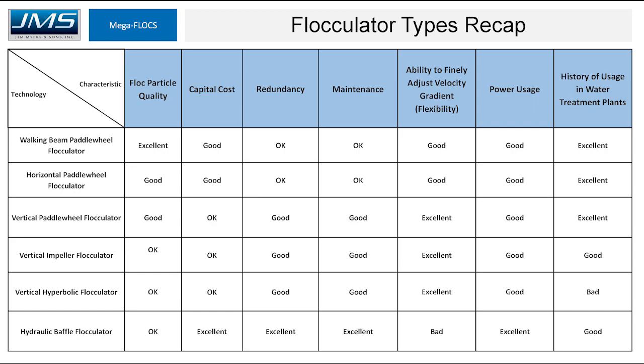To recap, each technology is listed by floc particle quality: walking beam flocculators are at the top, followed by horizontal and vertical paddle wheels, and then the other flocculators below in quality. As far as capital cost, the baffle wall flocculator is the lowest. The horizontal and walking beam are the next lowest if you amortize the drive cost over many reels, and then the vertical types have moderate capital costs. For redundancy, the baffle wall has no moving parts and will always function. Next would be the vertical units where if one goes out there are usually several others still functioning. The walking beam and horizontal have just one drive.